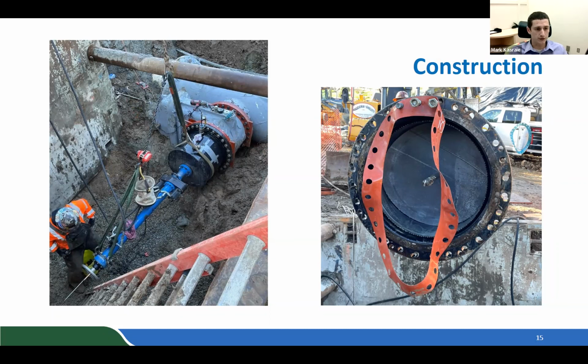And once the gate valve closes, the machine can depressurize and get removed from the pit. And we essentially have a point of connection ready to go. And so the photo on the right shows the removal of the machine and the cutting bit, and you can see the coupon is safely within the cutting bit there, which indicates a successful hot tap. So this was a big achievement for construction.